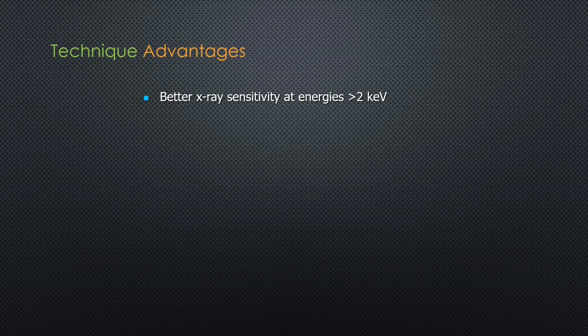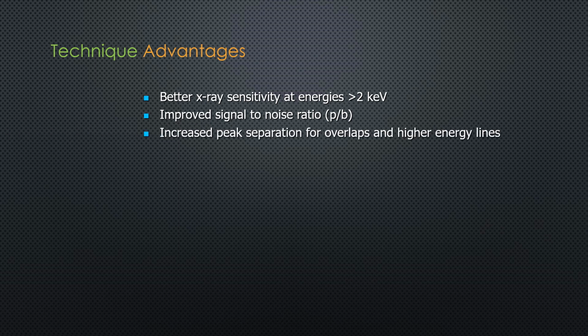Micro XRF offers better sensitivities at energies above 2 keV. Micro XRF offers a very low background, which gives an improved signal-to-noise ratio or peak-to-background ratio compared to traditional EDS systems. With Micro XRF, we can run at 35 to 50 kV. This allows us to excite the higher energy lines.